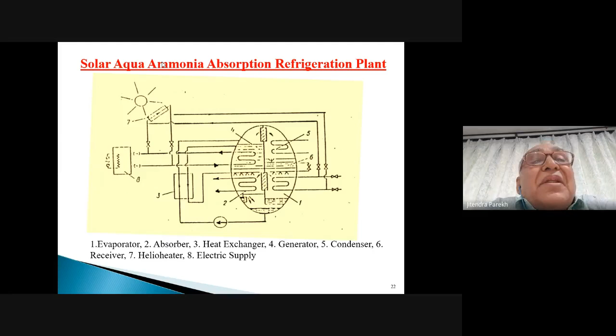Now these are some of the advantages I have shown as compared to the compression systems with the absorption. Reduction in the dependence on electricity up to 90%, with very little maintenance and spares requirement. Sub-zero temperature, right down to the minimum of minus 30 degrees centigrade, is possible without going into vacuum. Flexibility in desired temperature is possible without going into the vacuum, and without reduction in the plant capacity. Simple, noiseless, and vibration free.